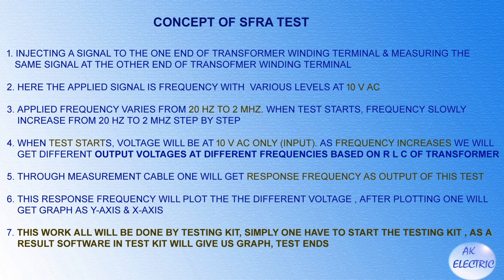In the SFRA concept, a signal is injected to one end of the transformer winding terminal and measured at the other end. The applied signal is 10 volt AC with frequency varying from 20 Hz to 2 MHz. When the test starts, frequency slowly increases step by step. As frequency increases, different output voltages are obtained at different frequencies based on the RLC of the transformer. Through the measurement cable, the response frequency is captured and plotted as a graph with Y-axis and X-axis.